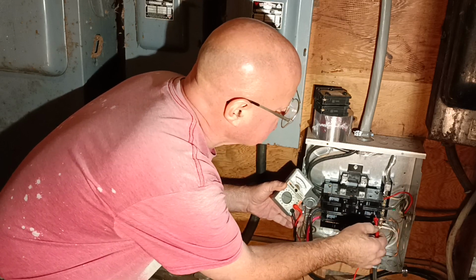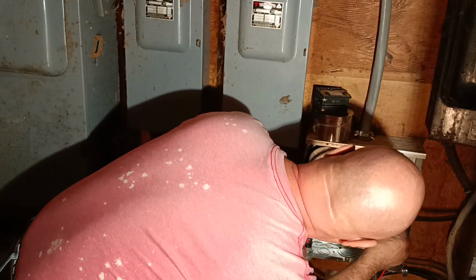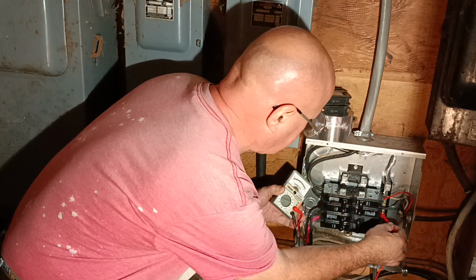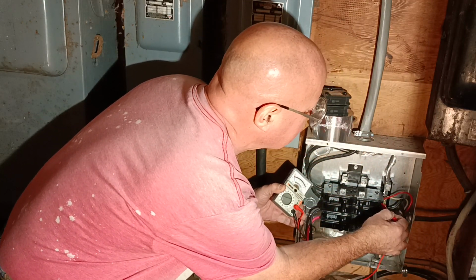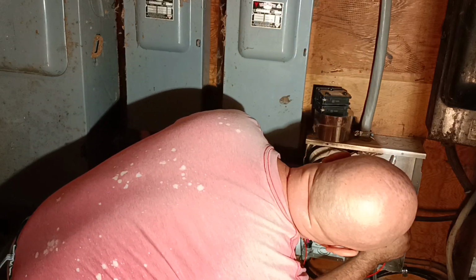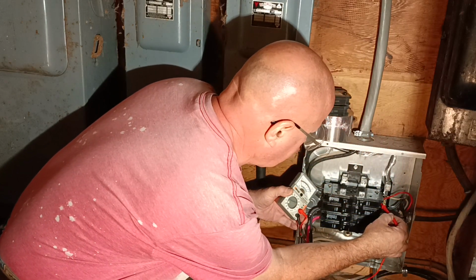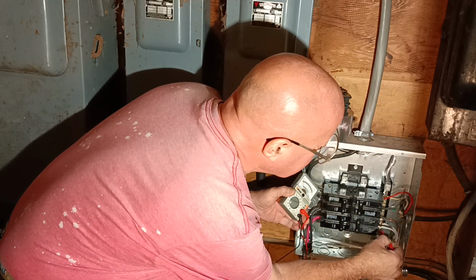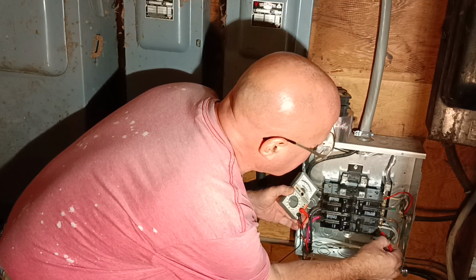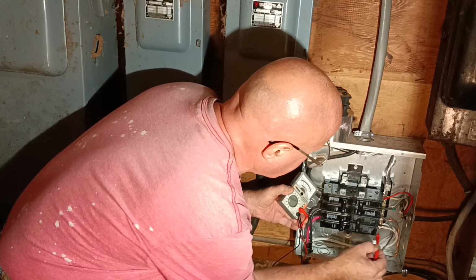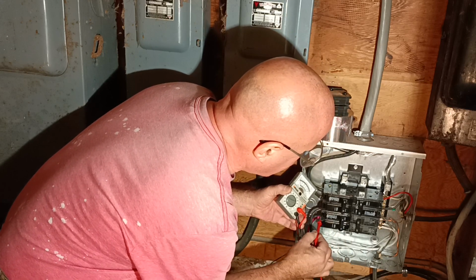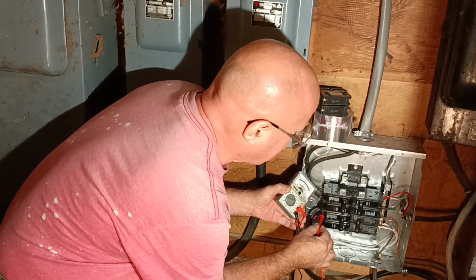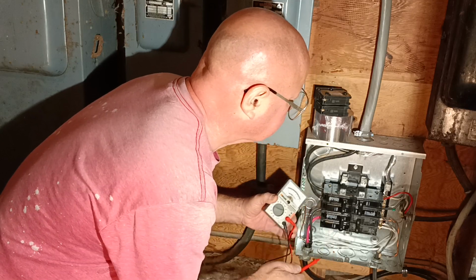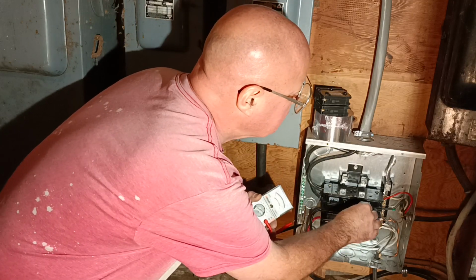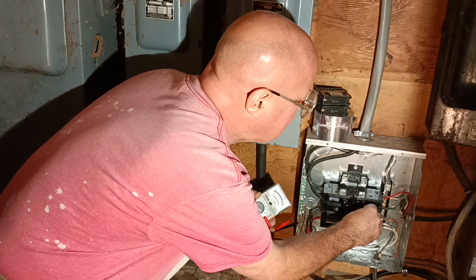Okay, this breaker is on. And we are not getting any power through this breaker. And we have no power coming through this breaker. This one has power. This one has power. This one has power. That one has power. So we have to change this 30 amp breaker out.